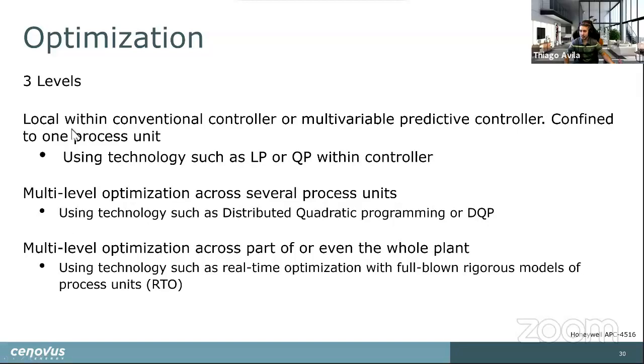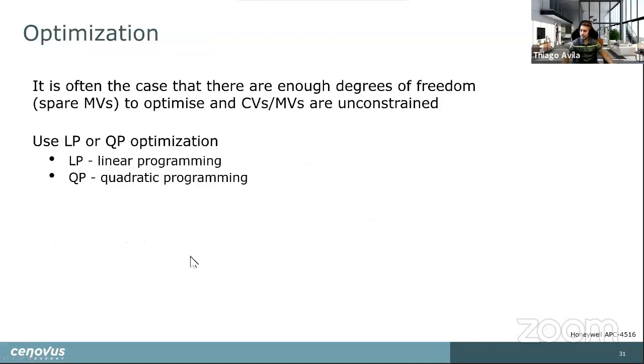You might use this if you have like certain pipeline nominations or sales commitments and you have a distributed set of production facilities and you want to optimize your sale agreement across very different facilities that aren't really related on the operating level. Most of the gains with APC are at the second level. First, to get the unit stable, you're operating within the ditches and you're optimizing to the best of your knowledge at the local level. And then once you start coordinating the different controllers together, the majority of your incremental savings are here. And you can only do the optimization if you have extra degrees of freedom. So you need more MVs than you have CVs to be able to do optimization.